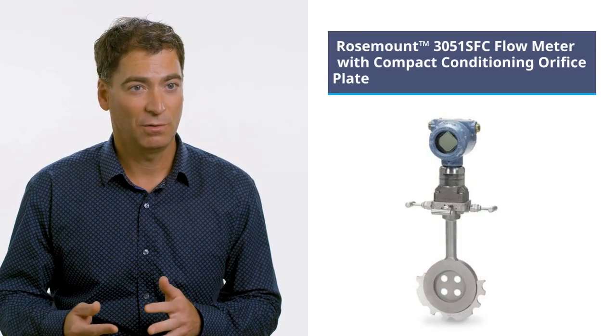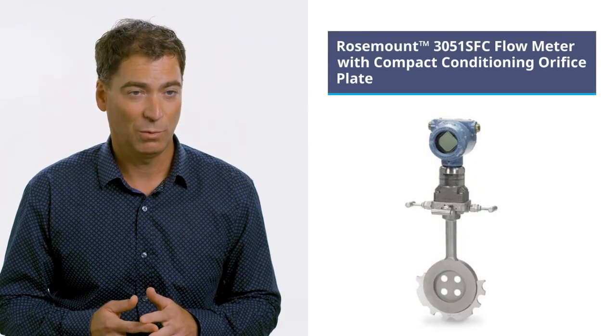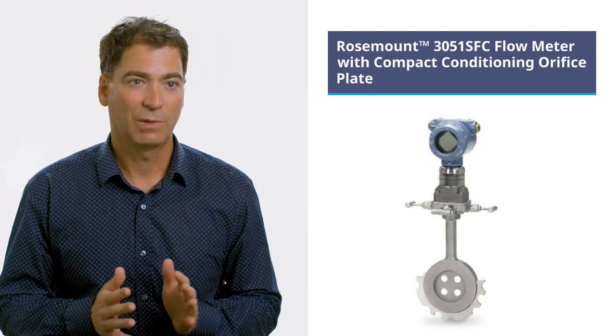The nice advantage of the conditioning orifice plate that we can use for water flow measurement is that it does not require a lot of upstream or downstream space. A lot of times these electrolyzers are manufactured in modules, so things need to be nice and compact. So this can really help you with the different technologies. We can pick which makes the most sense depending on the need of the customer.